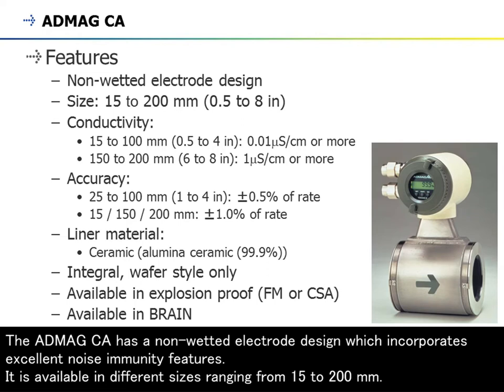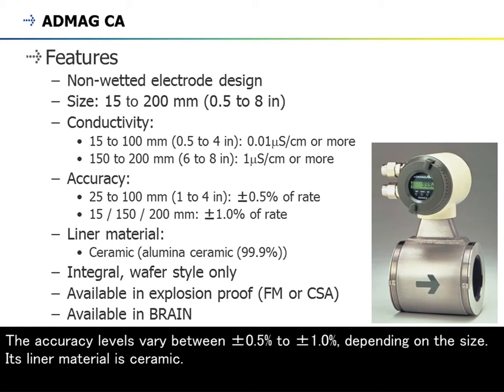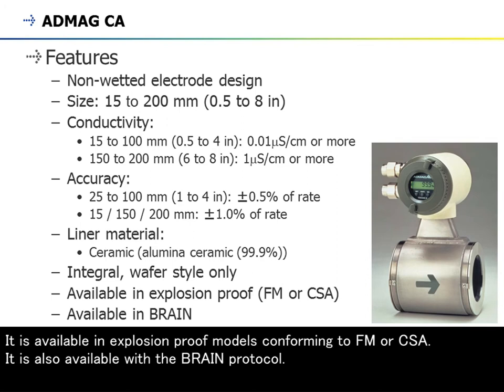The ADMAG CA has a non-wetting electrode design which incorporates excellent noise immunity features. It is available in different sizes ranging from 15 to 200 millimeters. The ADMAG CA is suitable for ultra-low conductivity measurement ranging from 0.01 microsiemens to higher conductivities depending on the flow meter size. The accuracy levels vary between plus or minus 0.5% to plus or minus 1.0%, depending on the size. Its liner material is ceramic. It is available in explosion-proof models conforming to FM or CSA, and is also available with the BRAIN protocol.